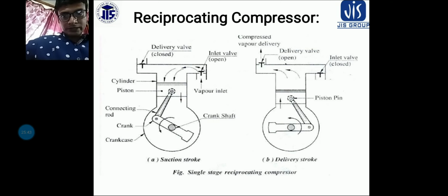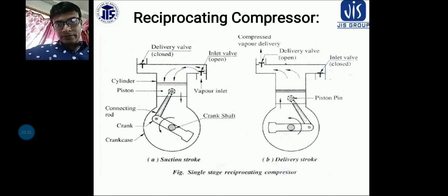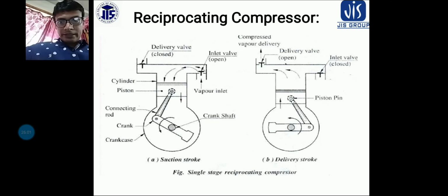In case of the first one, the open type, it is flexible in the sense that by varying the speed of the compressor, different capacities can be obtained, and it can be operated by any type of prime mover, such as an electrical motor, petrol, diesel or steam engine. In the field, the motor can be easily changed in case of motor burnout, and the refrigeration system is not affected by burnout.